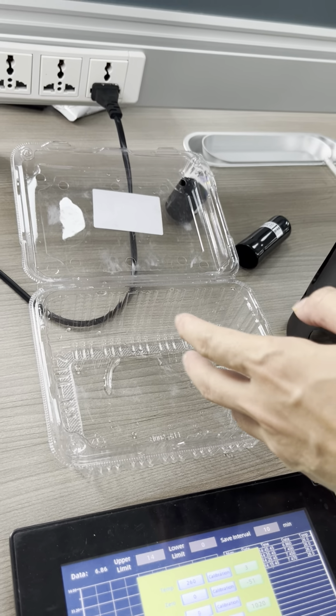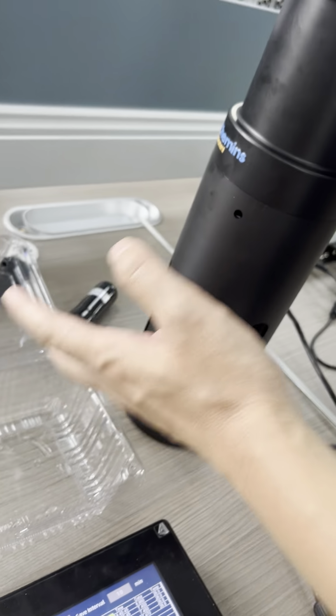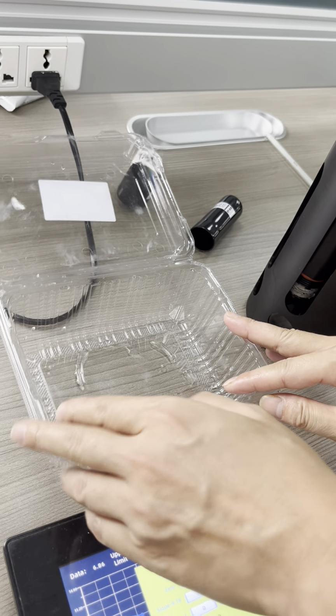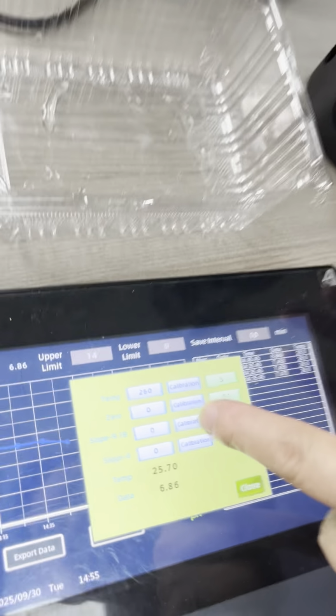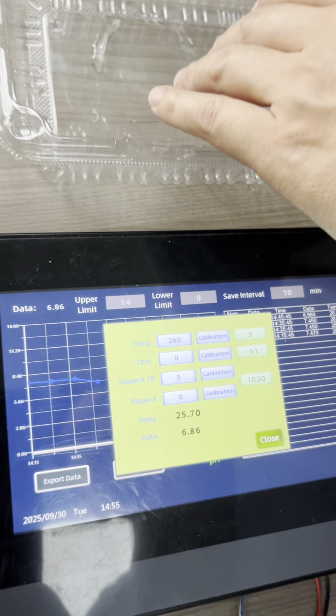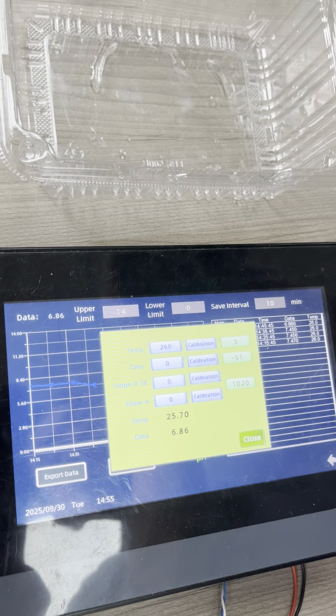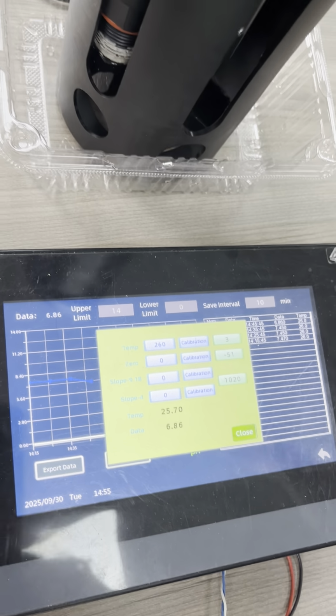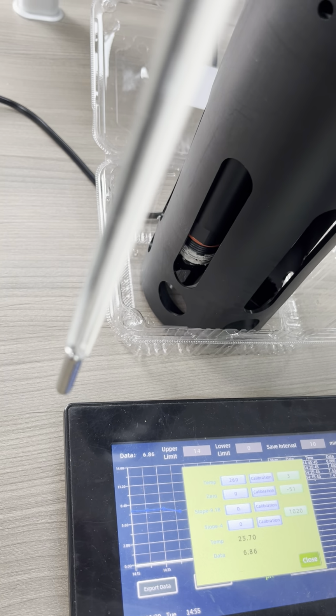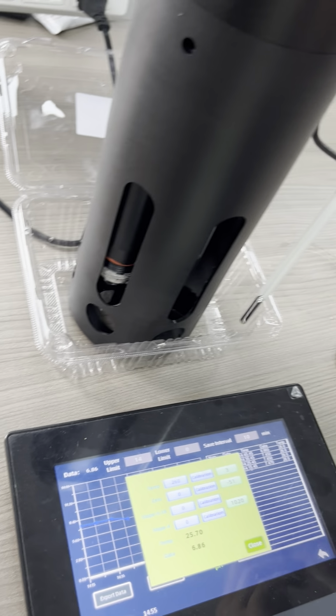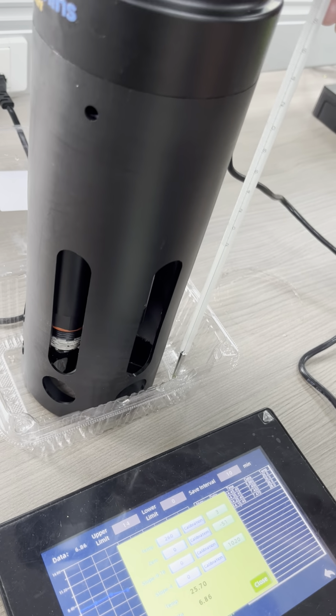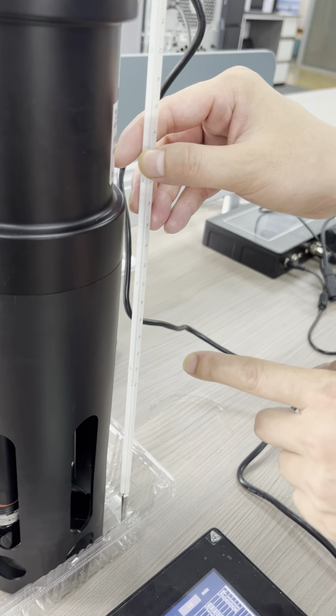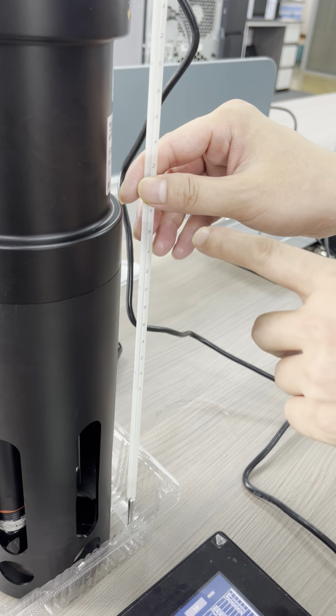We put the sensor into clean water. Let's suppose this is the standard solution. Now, for the temperature calibration, we can use clean water. Put the sensor into clean water. Then you use a temperature measurement instrument to measure the temperature. Let's suppose the temperature, when it's stable, is 26 Celsius.